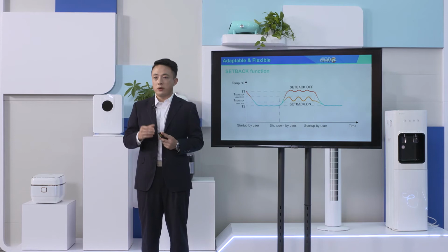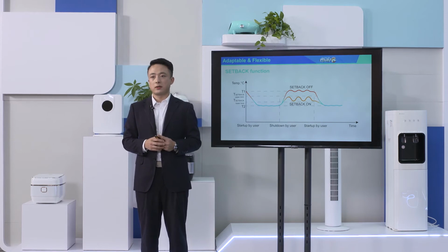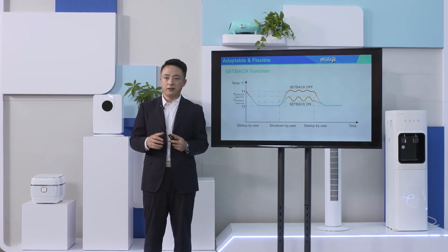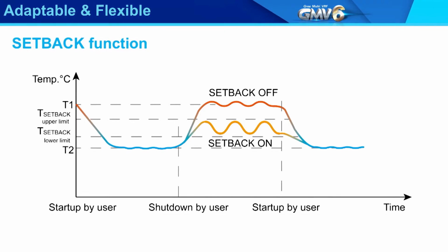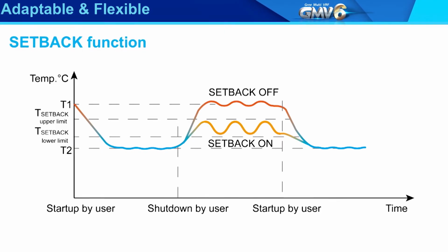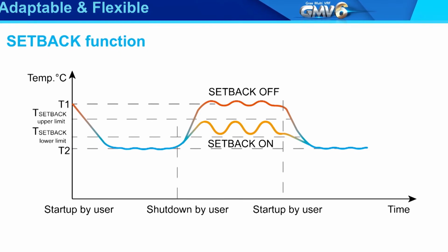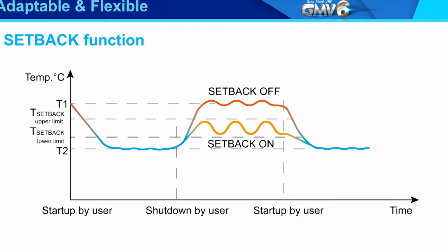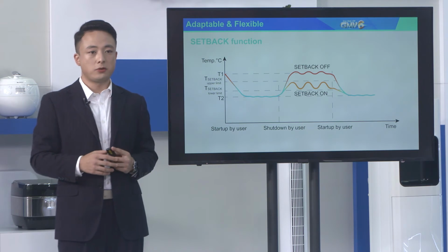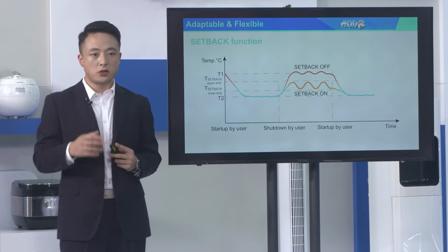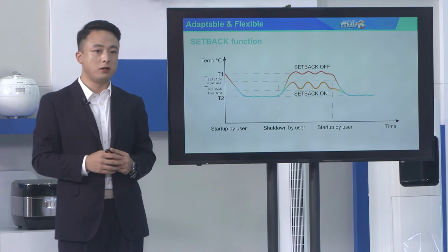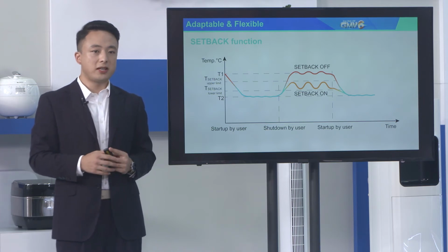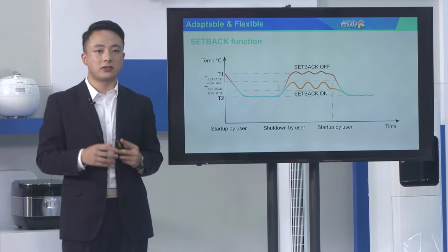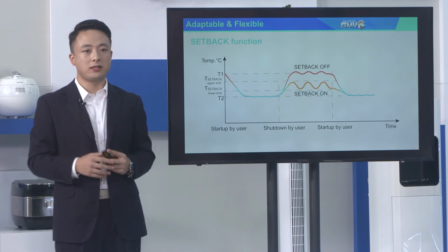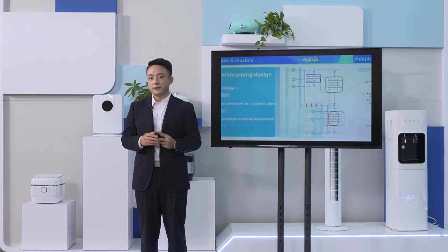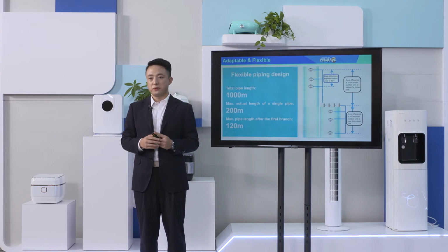In places where high levels of comfort are required, such as upscale hotels or high-end office areas, the setback function will let the system automatically judge the indoor temperature to start or stop running itself. By setting the upper and lower limits through the wired controller, the indoor units corresponding to the wired controller will start cooling when the indoor temperature exceeds the upper limit and start heating when the indoor temperature is below the lower limit. For installation, GMV6 has a good improvement.